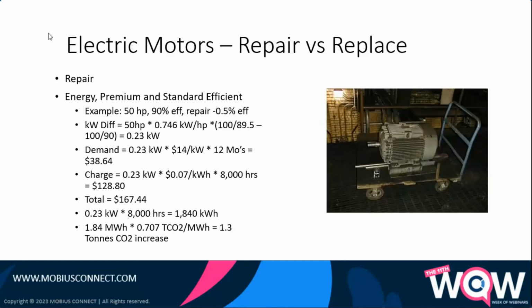Now, if I repaired it, one of the things we found through the DOE, actually the Canadian Electrical Association studies in the 1990s, was about an average of a 0.5% reduction per repair of a standard efficient electric motor. We did find out later at Hydro-Quebec that with the newer core steels for energy and premium efficient motors that didn't have as big an effect, but we'll use that for this example. Say a bearing wasn't installed right, or something's a little tight. That would also account for a 0.5% reduction in efficiency.